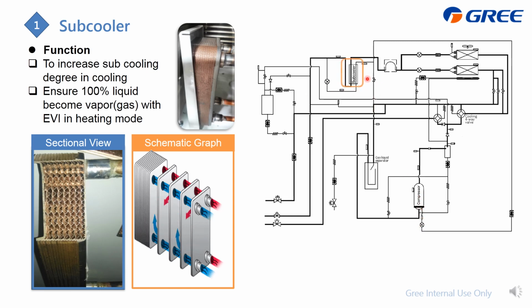And here is a question. This is a subcooler solenoid valve. My question is, during heating with EVI, will this be on or off? The answer is it should be off, because it is connected here. This is the gas liquid separator, which is the low pressure side. If this is turned on, the refrigerant will absolutely go to the gas liquid separator, because it is low pressure, and on the other side it is the middle pressure, so it will always go to the low pressure side.